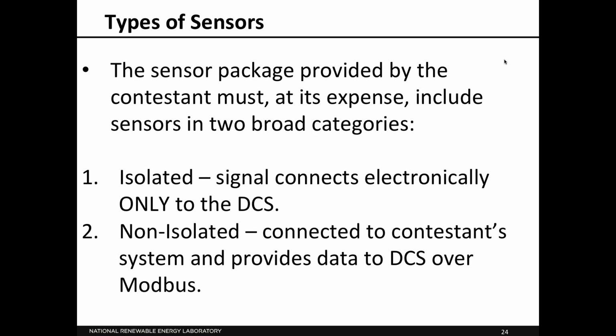Those two types of sensors are isolated ones, and isolated sensors are ones where the signal connects electronically only to the DCS. So physically, the physical parameter it's measuring, say pressure or a valve position, will connect to your system, but the electronic signal coming out of it will only connect to the DCS. Non-isolated sensors will be able to connect electronically to your controller, your PLC, which will then relay the data over Modbus to the DCS.